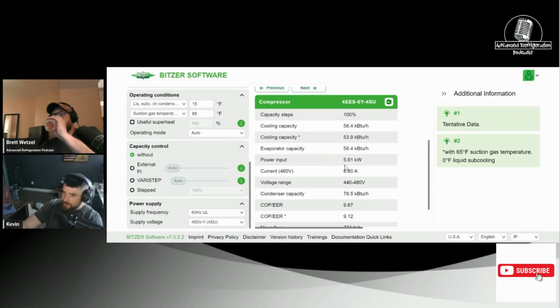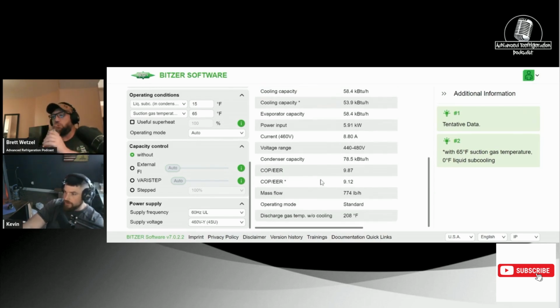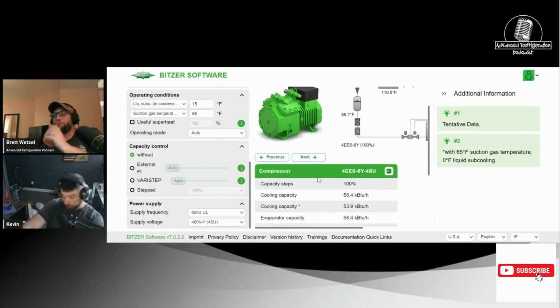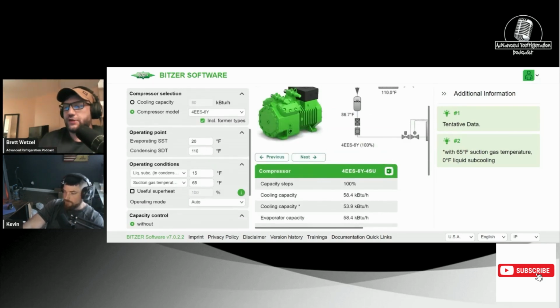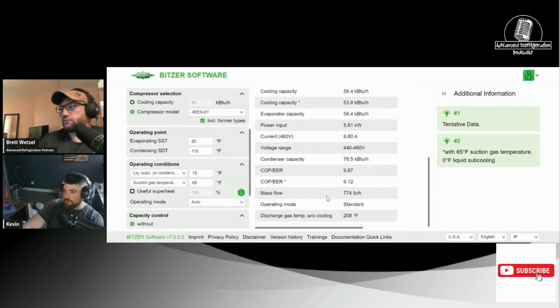So at a 20 degree saturated suction temp and I think it was 110 condensing. 120 here, 110, yeah, and 20 degree SST. So this compressor is going to draw 8.8 amps, and then with that suction temperature, we're going to be discharging 208 degrees. Okay. Now watch what happens when Brett changes the conditions.